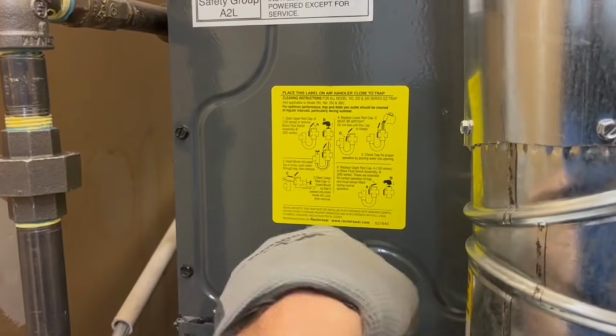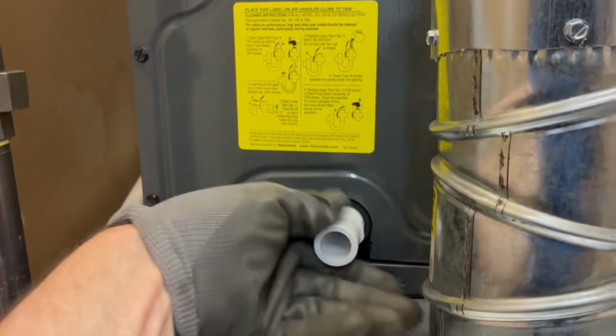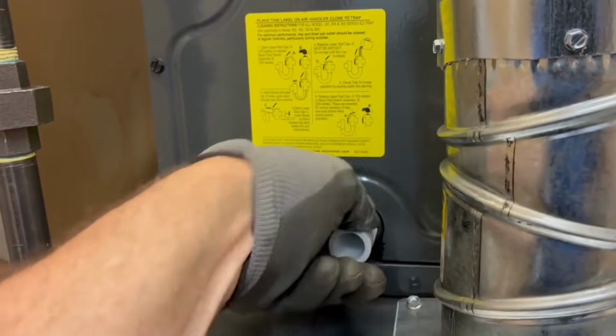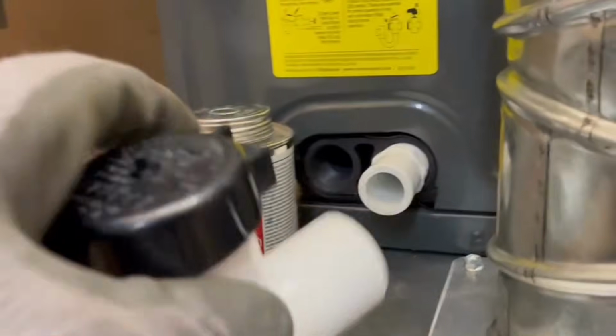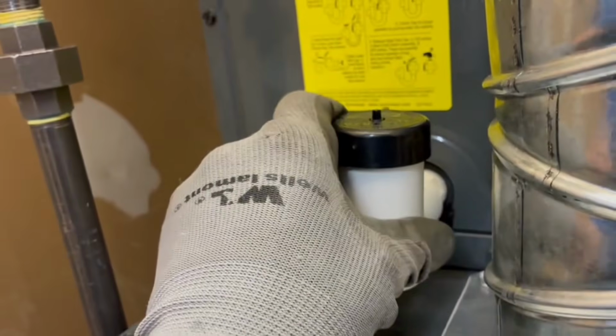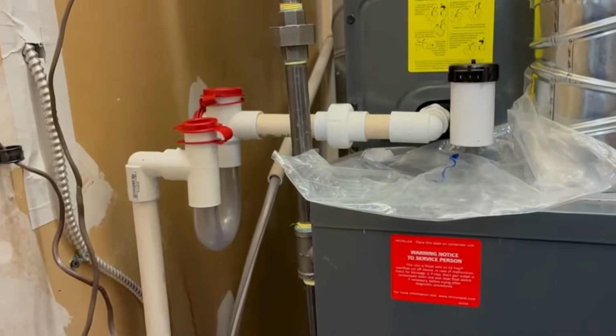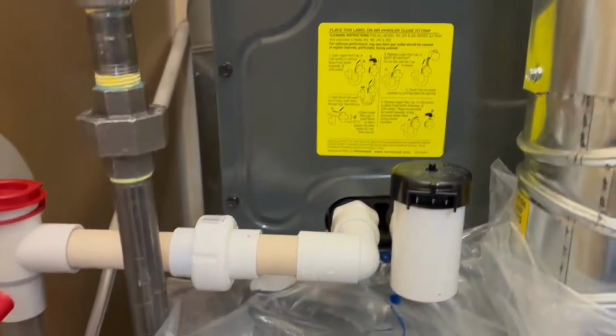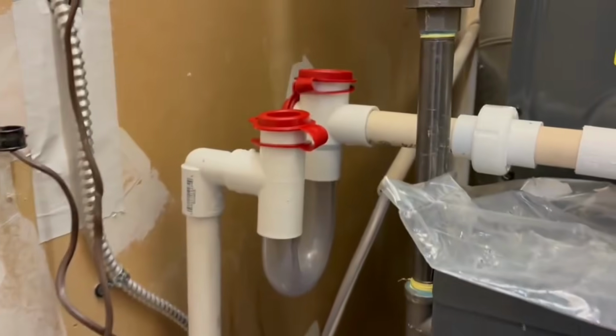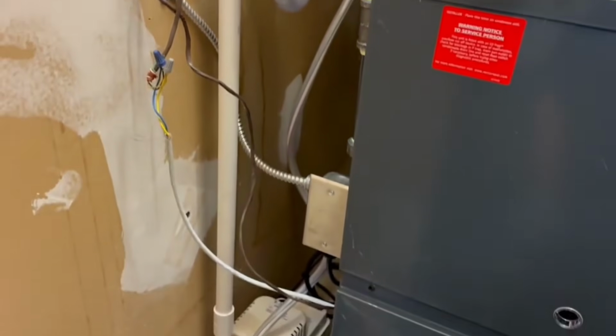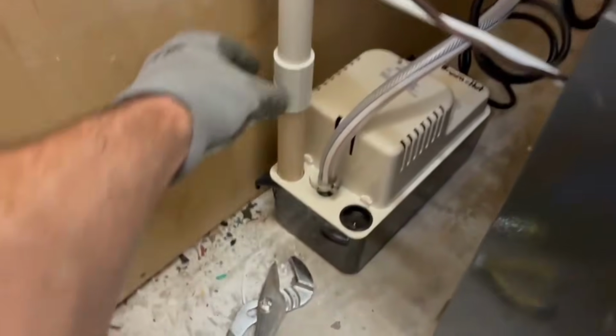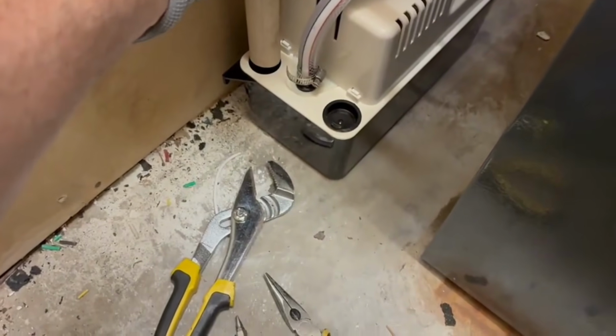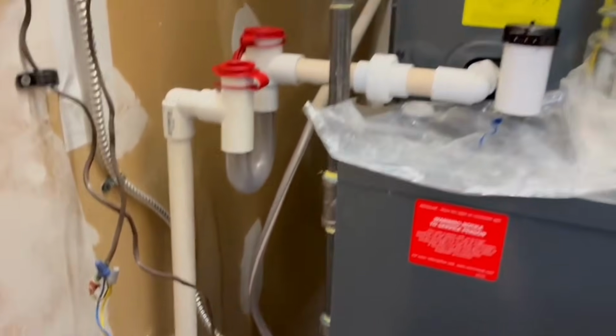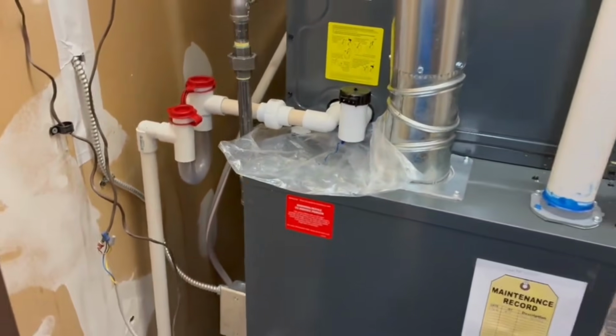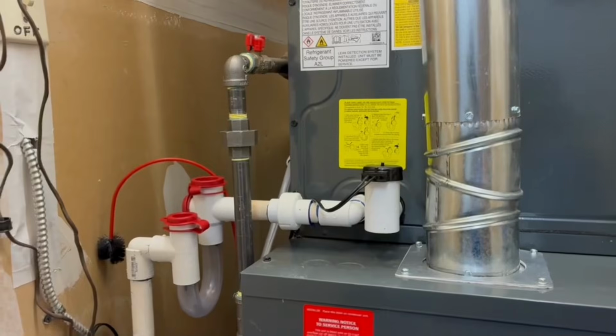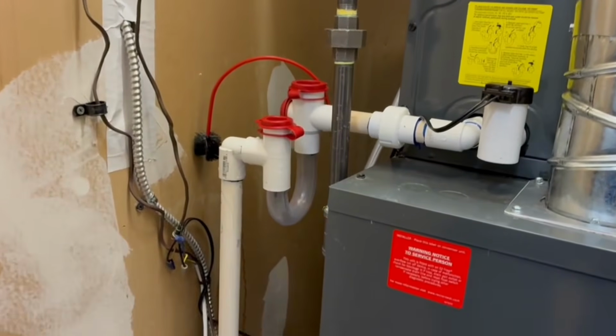So I like to dry fit everything first. This is the safety switch, just a float switch. And then I dry fit all of my condensate P-trap here. This one's nice because you have clean out ports and a clear P-trap. And it goes down to a condensate pump because we don't have a floor drain nearby. And we're leaving an air gap at the end of that pipe that you see, so it's not going to be sitting in the water. And it goes out the tube, up out the back of the suite to the nearest floor drain. We glued everything together. Got our sediment trap on our gas line.